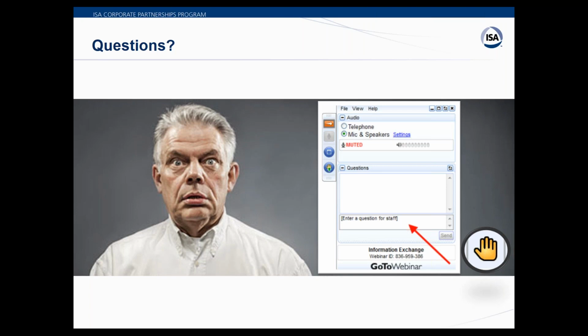Okay. We have more audience members joining the conversation, so I'll just keep on going with their questions. Is it mandatory for a pressure transmitter and a temperature transmitter in flow metering streams to be calibrated in a specific interval? No, I don't think it's mandatory. But depending on your industry, there could be some requirement that mandates that. But we've done other presentations, and my position is always do some tests and figure out what the drift is and come up with the optimum interval. So if you're trying to be very accurate on your flow measurement, you're probably going to have to go out more often.